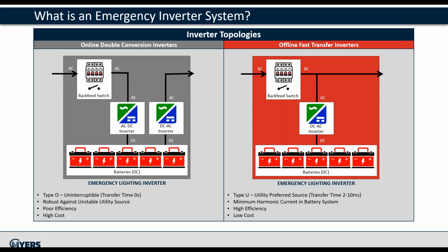Since the DC to AC inverter is actively powering the load all of the time, there is no transfer time when utility power fails, and it's fairly robust for areas with unstable power grids, such as third world countries. The disadvantage of the double conversion topology is poor efficiency because of the two conversion processes, higher cost, more opportunity for failure with increased parts and complexity, and also high harmonic ripple current in the battery bank, which reduces the lifetime of the battery.